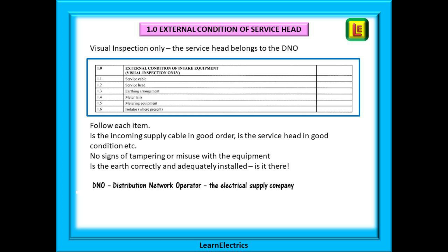Section 1 has six items listed, 1.1 through 1.6. Things to check include: is the incoming supply cable in good order? Is the service head in good condition? There should be no signs of tampering or misuse. Is the earth correctly and adequately installed — in fact, is it there? This is an inspection-only section. You or your customer do not own the service head — it is the property of the DNO. If anything is wrong, it should not be you that puts it right; your duty is just to contact the DNO and request that they put it right.